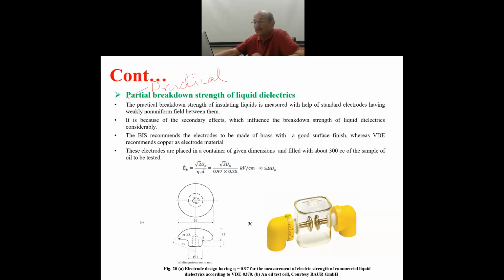The electrodes are placed in the container of the given dimensions and filled with the sample, and there is a standard procedure of making at least 6 readings. This is a very common practice all over power systems, wherever oil is used as an insulating material, because oil is still used for providing insulation as well as carrying away the heat generated within a transformer, with bulk of oil in very large transformers.